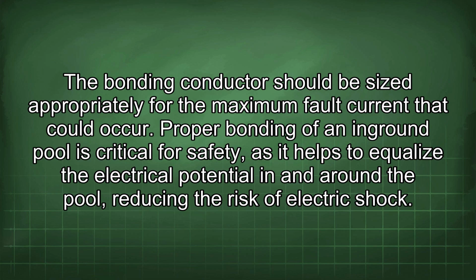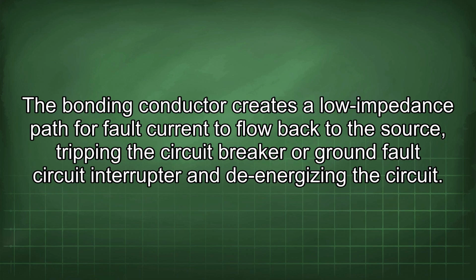Proper bonding of an in-ground pool is critical for safety, as it helps to equalize the electrical potential in and around the pool, reducing the risk of electric shock. The bonding conductor creates a low impedance path for fault current to flow back to the source, tripping the circuit breaker or ground fault circuit interrupter and de-energizing the circuit.